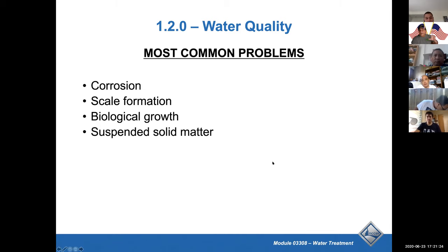Yeah, if you have a really high suspended solids and a lot of silica, it'll plate out in the hot condenser tubes and make a real fine scale, and it's almost like a glass on the inner tubes, and it really, really affects it. It's like trying to transfer heat through glass, and that doesn't do it very well, right? So that's what we're punching chillers for, the silica. Silica, yeah, and a little bit of calcium, because there's some calcium in the water too. And you're also getting some scale out, biological growth, things like that. So these four things: corrosion, scale formation, biological growth, suspended solids. That's a big problem in air conditioning plants because it affects heat transfer, right?